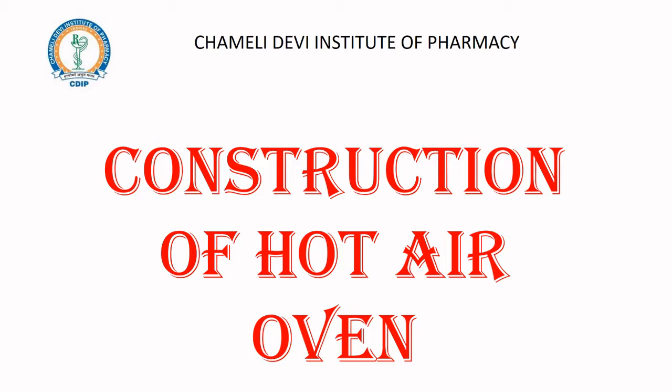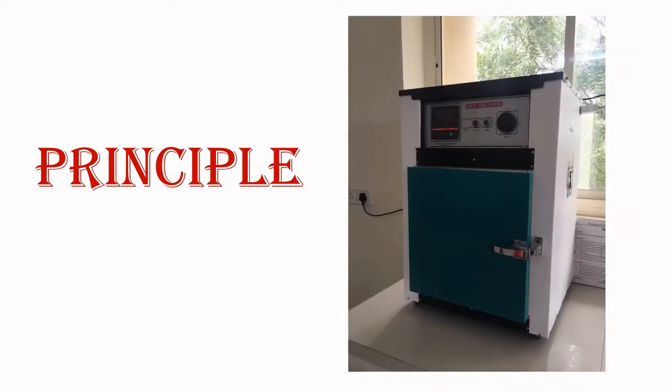Hello and welcome to the YouTube channel of Chameli Devi Institute of Pharmacy. In today's session we are going to learn the construction of hot air oven. Hot air ovens are one of the very utilized instruments for the purpose of sterilization. Sterilization is a process to remove all kinds of microorganisms from the given object. It is an absolute term — either the object will be 100% sterilized or it will be 0% sterilized.